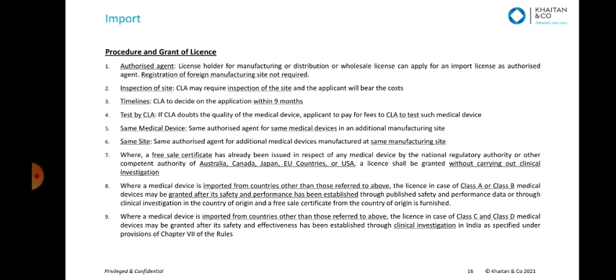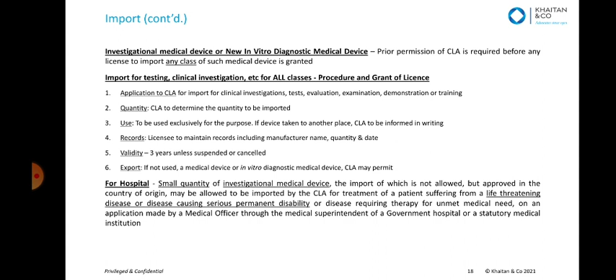Again, for an investigational medical device or new in vitro diagnostic medical device, if you are importing, you need a specific license. You have to apply and get the licenses specifically for the use, and the validity of the license is 3 years, and you can export it if it has not been used and the authorities permit you to export it. Wholesale and retail licenses continue to be governed by the Drugs and Cosmetics Rules, and the existing licenses continue to remain valid.